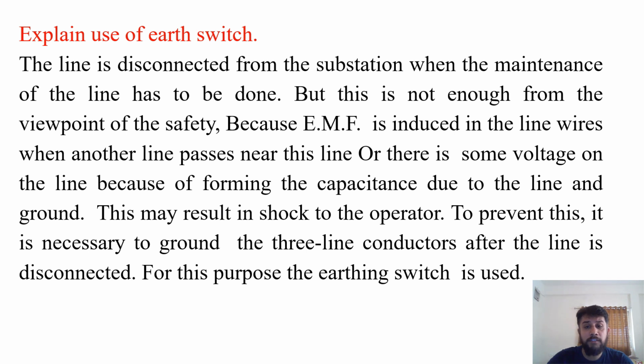Use of earth switch. If this question is asked in the examination, you have to write like this. When the line is disconnected from the substation, when the maintenance of the line has to be done, it is not enough from the viewpoint of safety, because EMF is induced in the line wires when another line passes near the line, or there is some voltage on the line because of the capacitance formed between the line and earth or the line and ground.